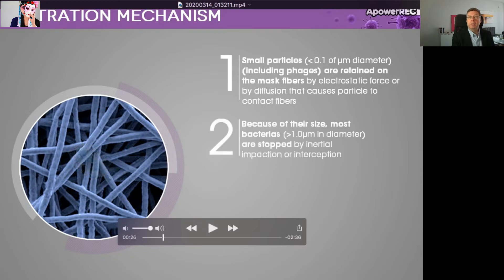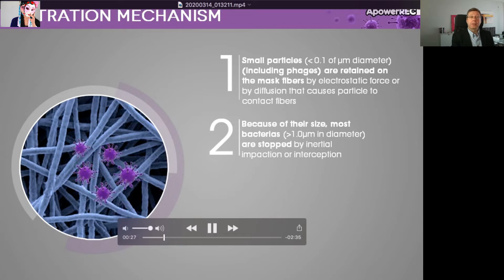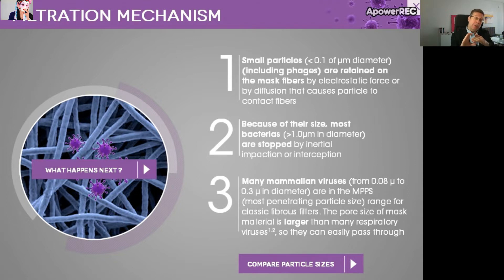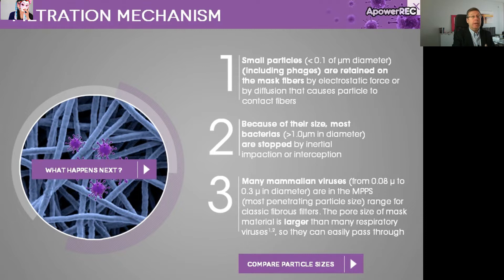Then of course we have the bigger particles, which are like bacteria, dust, fungus, spores, which due to their size, mechanically they don't fit to pass through. And then we have other particles which have a size called in the filter industry the 'most penetrating particle size.' These fit to pass through — they are heavy enough and big enough not to be attracted by electrostatic forces, and they are not doing the Brownian moves. Sometimes they will pass through; sometimes due to random position, impaction will hit the fibers and they will not pass through. Unfortunately, viruses are in this category — this most penetrating particle size.